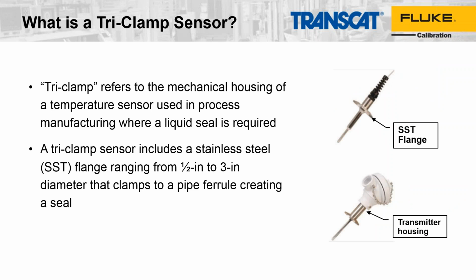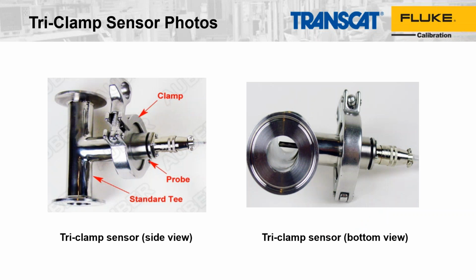So let's talk about why we call these tri-clamp sensors. Tri-clamp refers to the mechanical housing of the temperature sensor, so the temperature sensor can be installed easily into a tri-clamp system. And we'll have some more pictures coming up here to show you. The tri-clamp sensor is typically made out of stainless steel, or the entire assembly is made out of stainless steel. And the flanges that you can see vary in size from a 1/2 inch to 3 inch diameter. And again, the flange is on there to make it easy and efficient to install these in a manufacturing or a food production process.